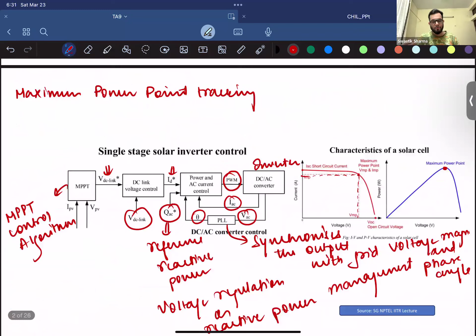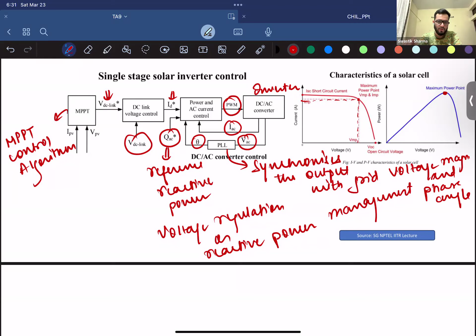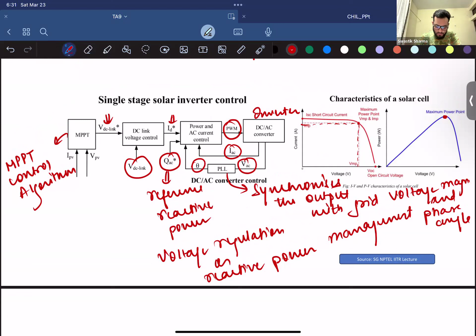The control algorithms give you the current to follow so that your AC current inverter's output is also mimicking the AC currents required from your output algorithm. But why only Id star is used in grid following inverters, I don't have a perfect explanation. But yes, it's due to Id star only because this Id star is what is taken out from the control algorithm which is controlling how your DC link voltage is behaving. That is how your AC current control is implemented for your solar PV inverter. But why only Id star? There's no rational explanation that I can come up with as of now.